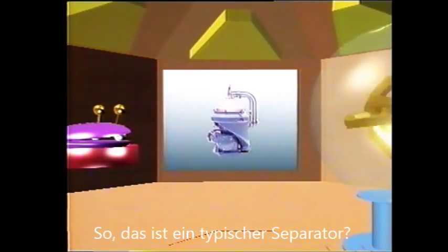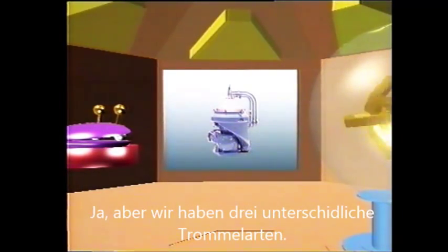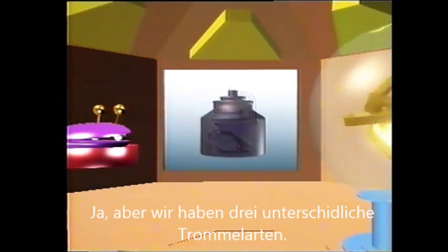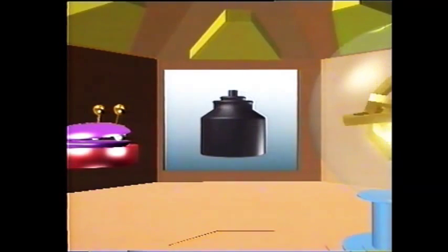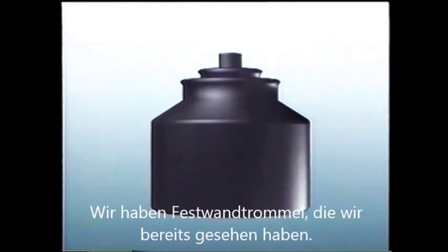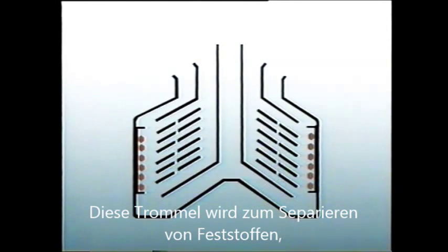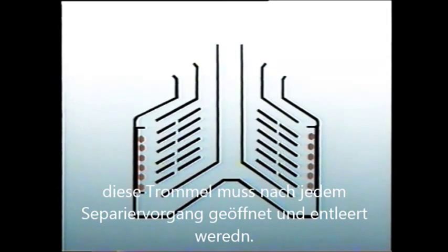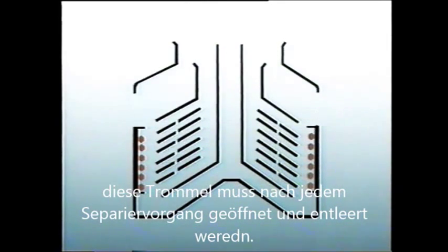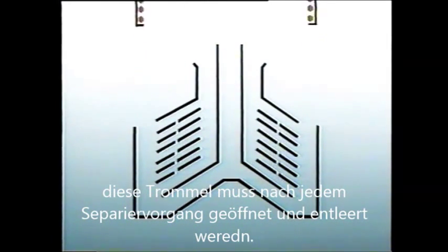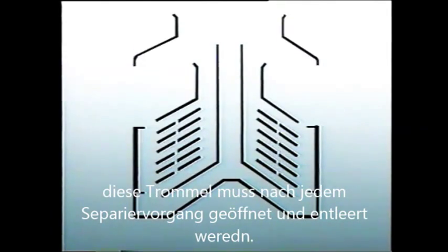The bowl is the most important part of the separator. If we then fit a drive unit and a cover, the result is a centrifugal separator. There are three main types of bowl available. First, we have the solid bowl centrifugal separator — it has a solid wall with no outlets. This type is a solids retaining separator, used for what is known as intermittent service. At the end of each run, the bowl hood is removed and any compacted solids are lifted out manually.